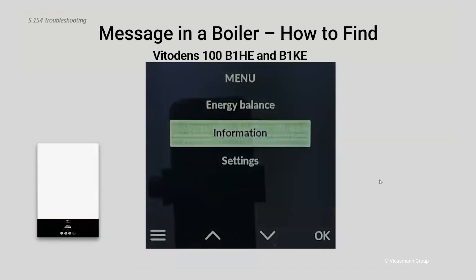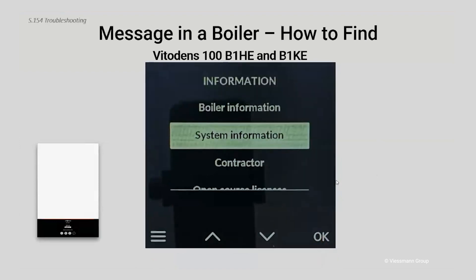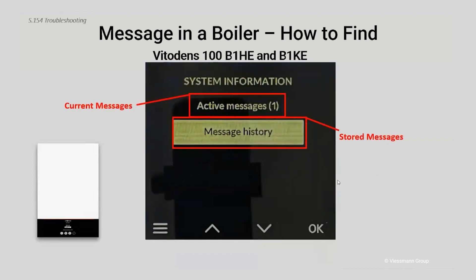Pushing the menu key is going to take us into the main menu. Scroll with the down arrow key to see 'information' highlighted, then push the OK button. From there you'll have different snippets of information — go to 'system information,' highlight it, and push OK. From here you have 'active messages.' If there's something causing that boiler to not work as you'd anticipate, you'll see an active message there — with a bracket showing one or multiple messages. You can highlight that active message, push OK, and see what that message is.